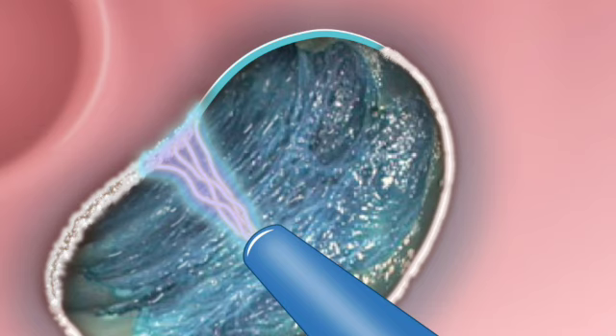Simple enough. Sure. But the third, and unequivocally the most critical variable, is duration. Time. The actual amount of time the physician keeps their foot pressed on the generator pedal. Exactly. The physics of thermal injury are strictly mathematical. Let's look at the joules. Okay, let's do the math. If the generator is set to 45 watts and the endoscopist activates the plasma beam for exactly 1 second, they have delivered 45 joules of total energy to the tissue.